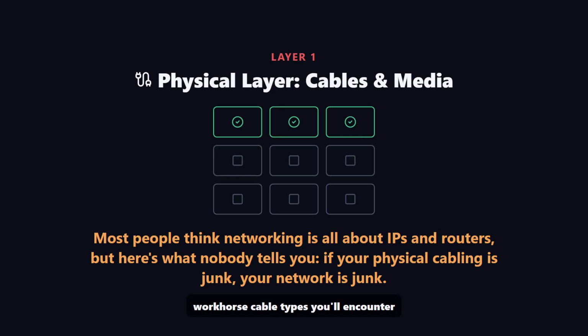Let's look at the 3 workhorse cable types you'll encounter in a modern enterprise. Cat5e twisted pair copper supports up to 1 gigabit per second at a maximum segment length of 100 meters. It's still the minimum spec for new installs. Cat6 also does 1 Gbps up to 100 meters, but it can handle 10 Gbps for shorter runs up to 55 meters, thanks to better shielding. And then there's fiber optic, immune to electromagnetic interference, able to carry 100 Gbps or more over kilometers. That's why you'll see fiber used as the backbone between switches in a building or between data centers. Know these 3, and you can already start reading the blueprint of a physical network.